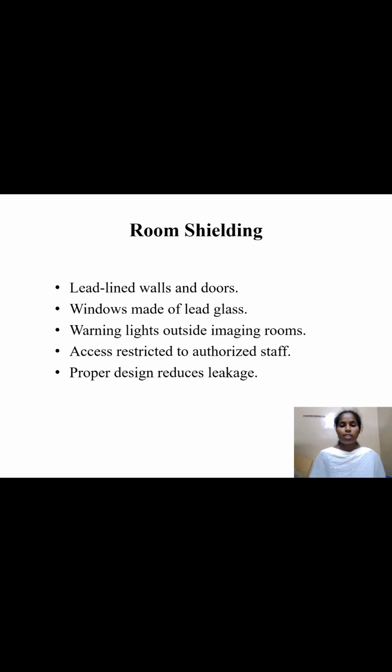Next one is room shielding. Imaging rooms are designed with lead-lined walls, doors, and windows. Warning lights outside the rooms indicate when radiation is in use. Access is restricted and proper shielding reduces radiation leakage, protecting the environment.